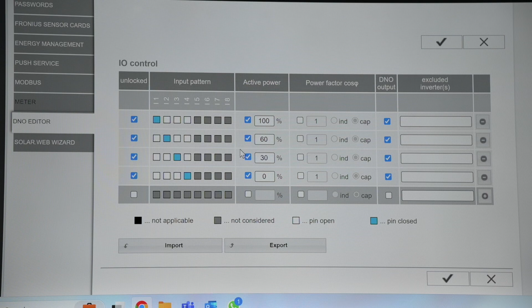And then we need to make sure that our priorities are set. Normally dynamic power would be the top priority. So we need to set the controlling at the top, followed by dynamic power if we had a smart meter still in the system, and then lastly our I/O control. Once we're happy, again, check mark. And then lastly the top check mark to make sure all settings are applied to the system. So that's if you are doing Victron coupled, as well as any genset integration or external PLC that's controlling the system itself. Exactly the same settings would apply. Depending on whether it's TCP Modbus or RTU, it will vary depending on what controller is being utilized. But that's how you would commission this. We have how-to videos available that run through the exact commissioning process. So if you are stuck, you can go to our how-to videos, which will demonstrate.